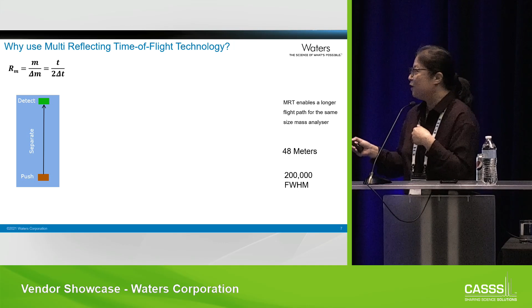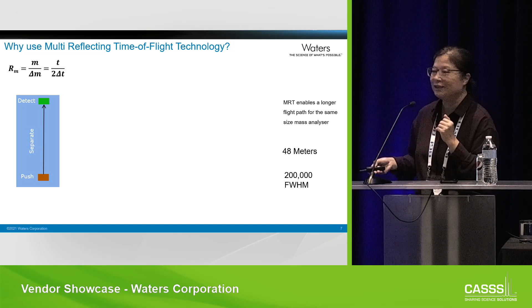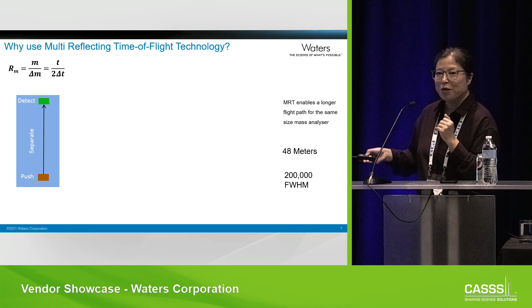So the way to improve or increase the mass resolution in a time-of-flight instrument is you can increase the flight path, okay? Now, in the original linear design, you have your ions being pushed into a detector in one direction. Now you can increase that one flight path to as long as you want, but that's not practical. You can't build an instrument like that. Then later on we have the V mode. V mode has built-in grid reflectron to deflect ions and make it V-shaped. So you actually double the flight path, and therefore you increase the mass resolution.